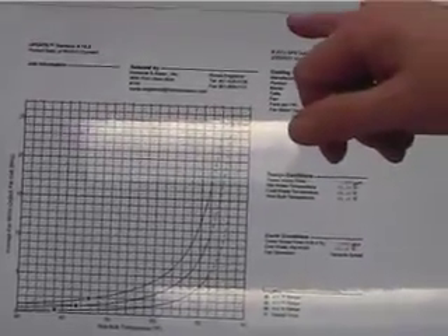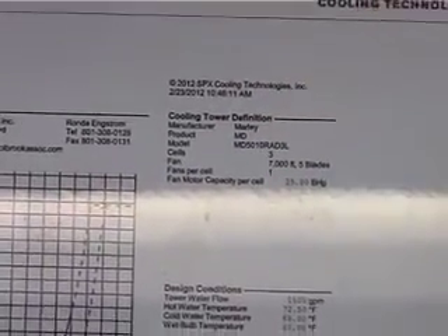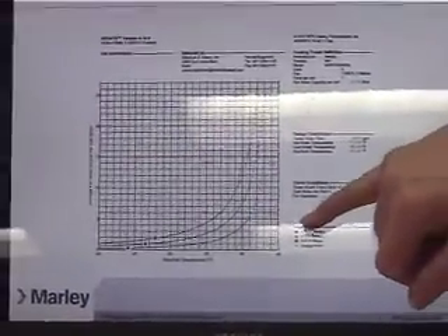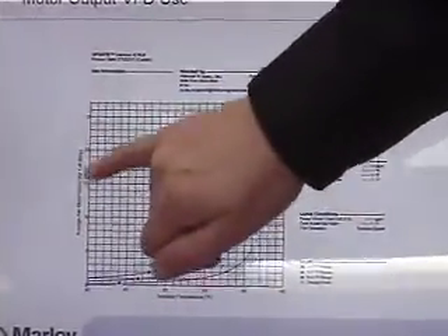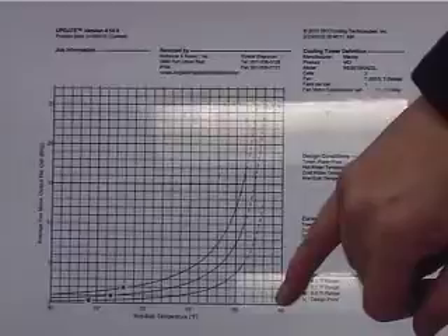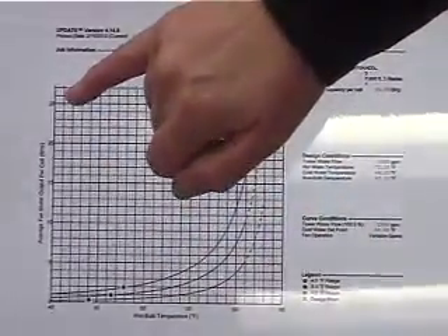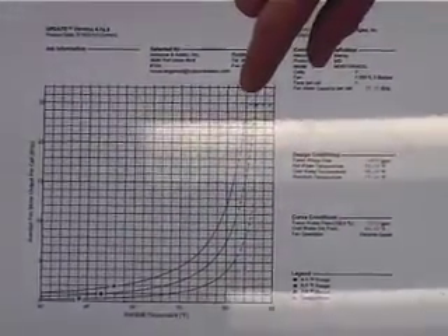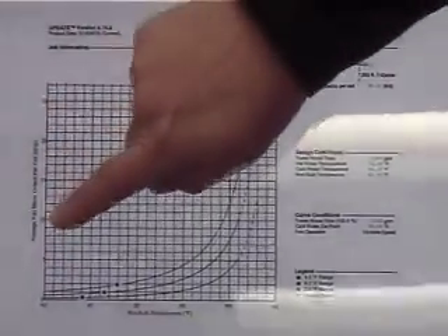The way that your cooling tower operates is with a VFD. This allows only the amount of horsepower for the motor that is necessary to achieve the cooling. This is a graph of the wet bulb temperature versus the fan motor output. As the wet bulb drops, so does your fan motor horsepower go down. So all of this, you have a 25 horsepower rated motor. This is all the money you're saving. These should just be dollar signs because of that VFD.